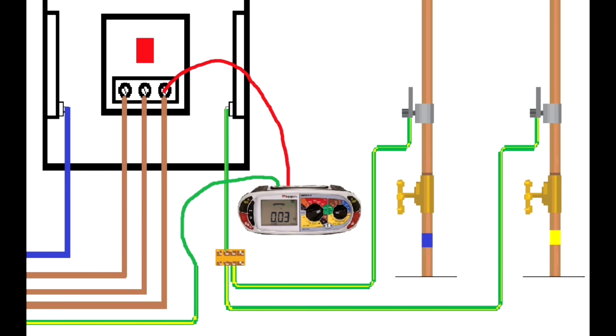And you note all parallel earth paths are removed because the earthing conductor was removed from the MET. We're now going to watch Matt perform the external earth fault loop impedance test on a three-phase distribution board where the earthing conductor and bonding were all within the distribution board, but remember to look at your AM2 or AM2S rig to see if there was an MET there, a main earthing terminal. If there was, you're going to need to perform the test as I've just described.